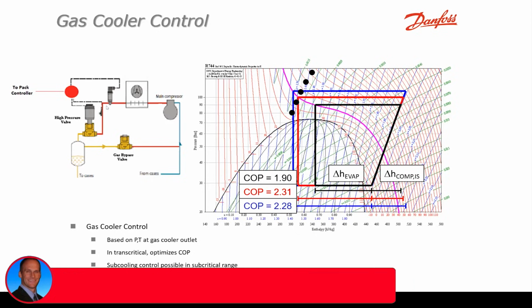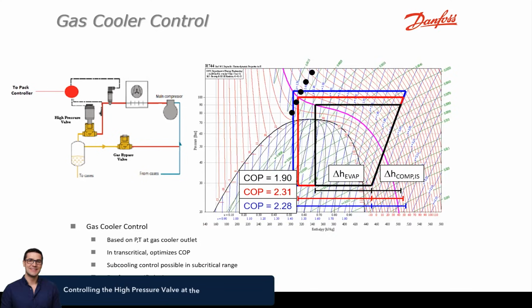So there's always going to be in this setup a temperature sensor at the outlet of the gas cooler. And we always stress the importance of that sensor being very close to the outlet of the gas cooler, within a few feet. Maybe if the gas cooler is up on the roof and the rack's down in a compressor room, we don't want that temperature sensor down in the compressor room. We want it as close to the outlet of the gas cooler as possible to really pick up the true temperature there, and insulated. We don't want any effects from ambient.